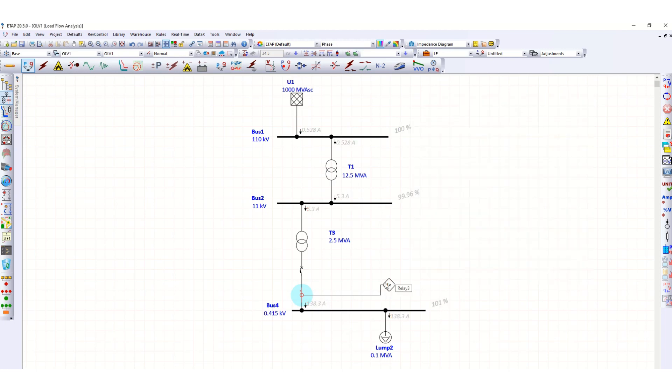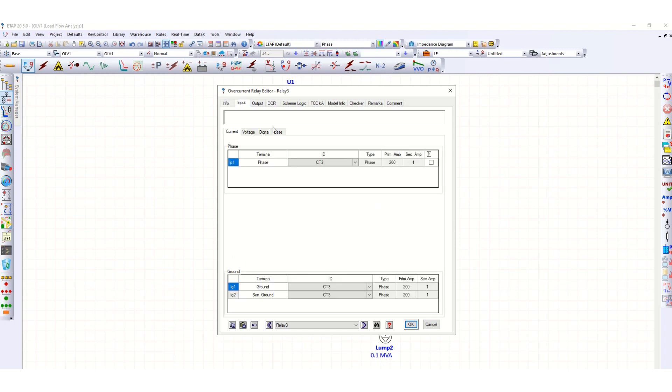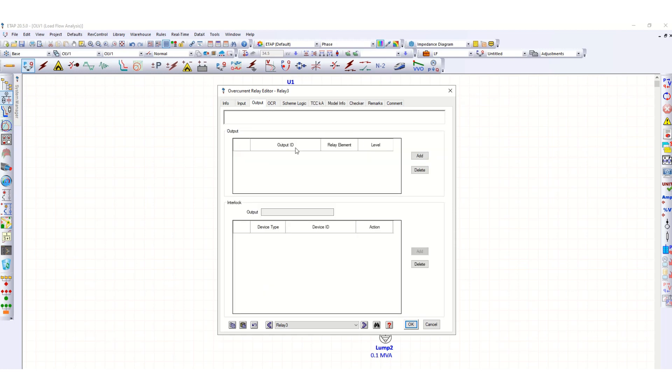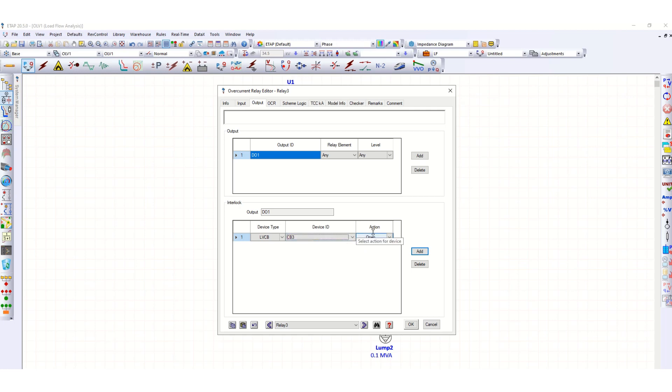Now let's define the value of this overcurrent relay. Go to input. It is connected, input is coming from CT3. Go to output, let's add the trip element. Let's click, this is LVCB and CB3, so in case of any fault this overcurrent relay will trip the CB3 breaker.